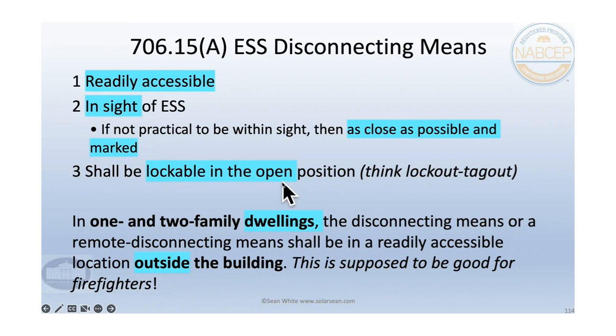Just for instance, with the Tesla Powerwall, there's a button on it. And if they could lock that button, if that little button on the side of the Tesla Powerwall was lockable, then that could be the disconnecting means, just a little button. It doesn't have to be some big, huge, high current rated, load break rated disconnector, anything like that. If that button would just turn off the inverter coming out of that Powerwall and be lockable, then that would work.